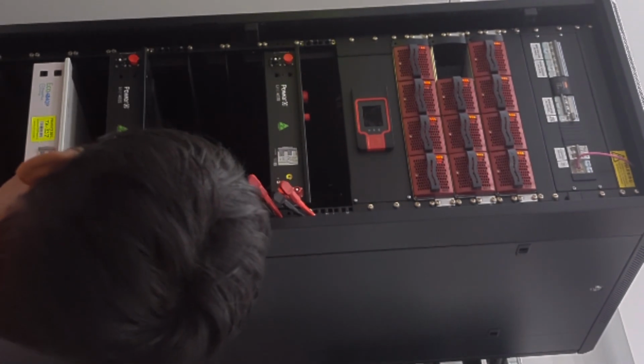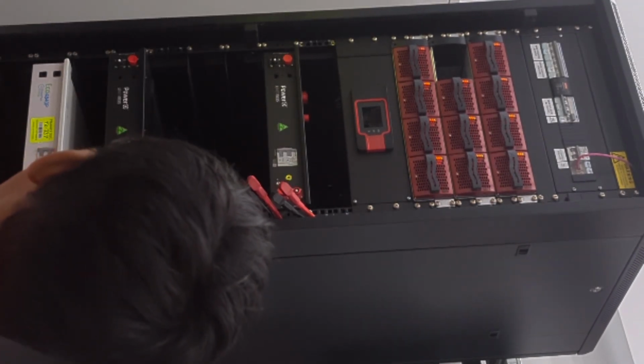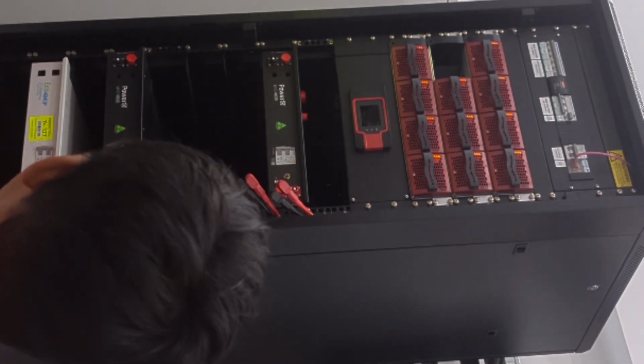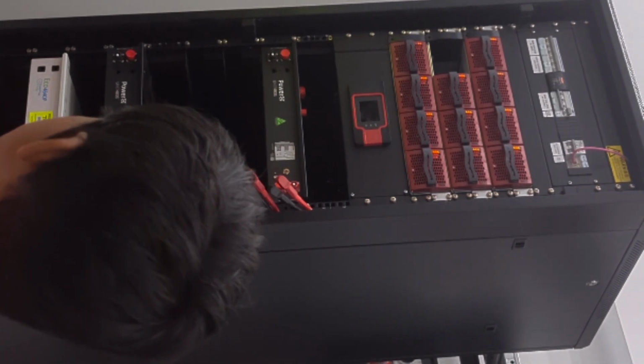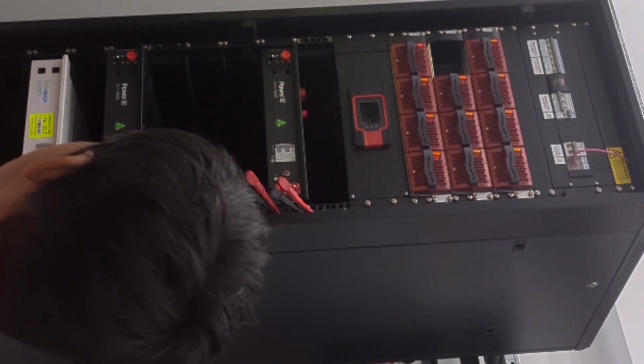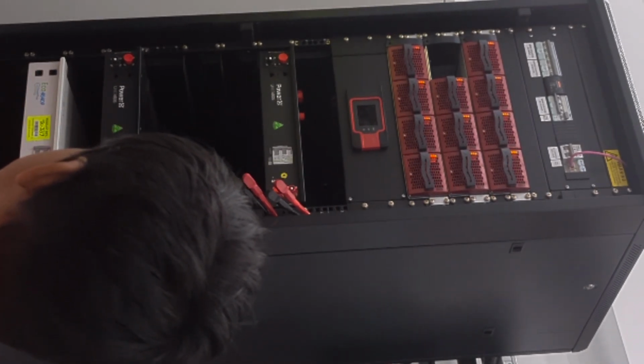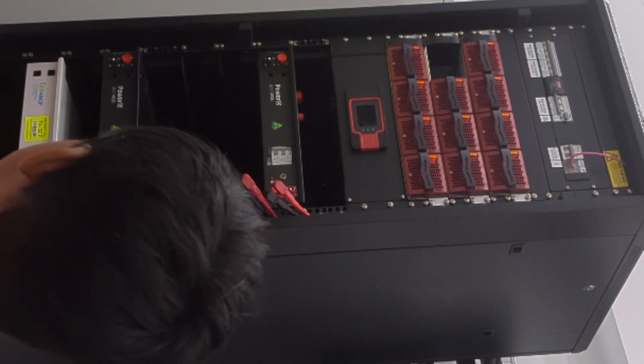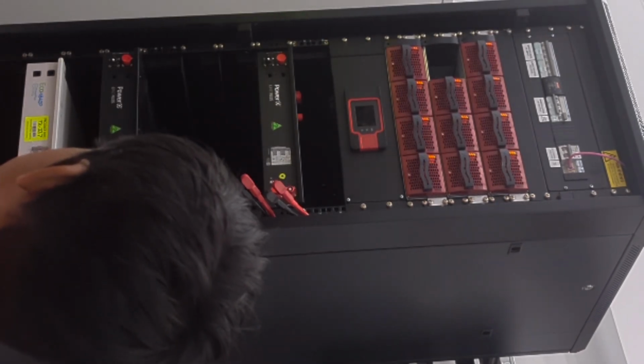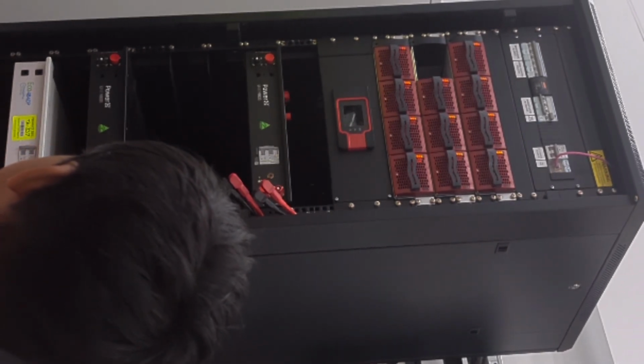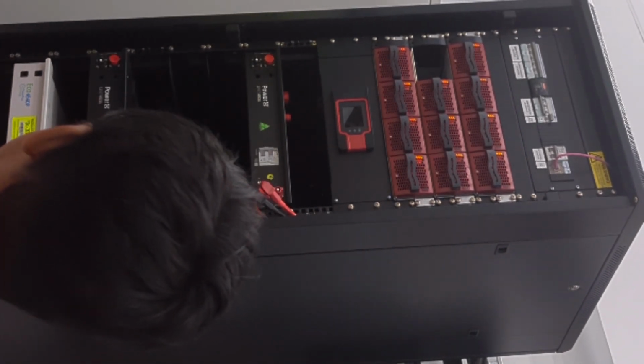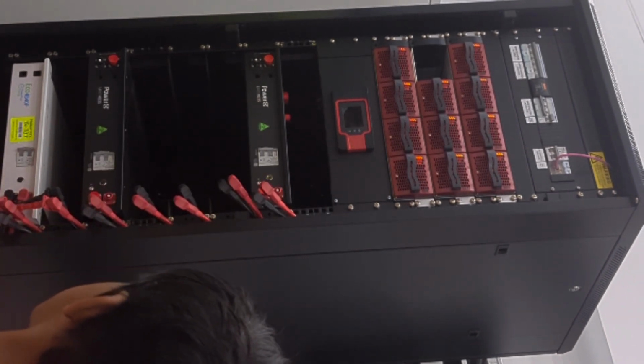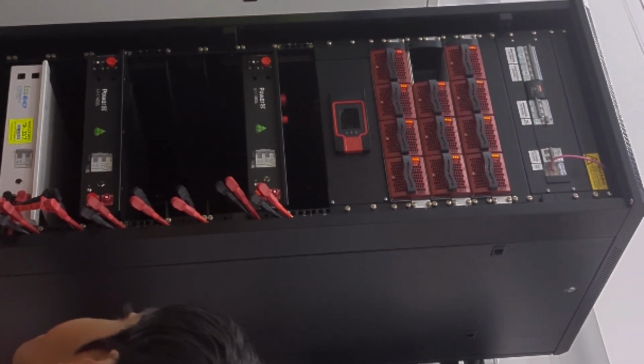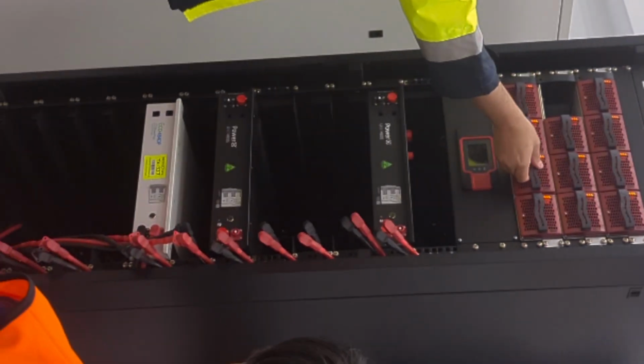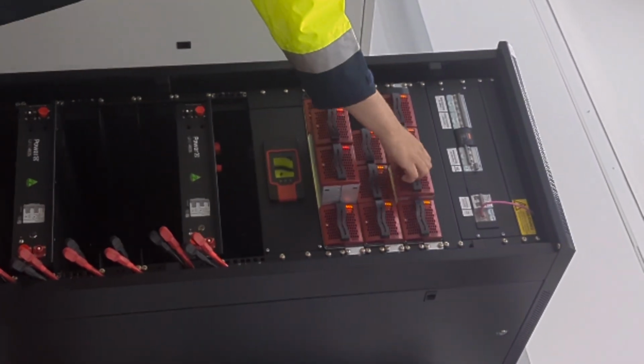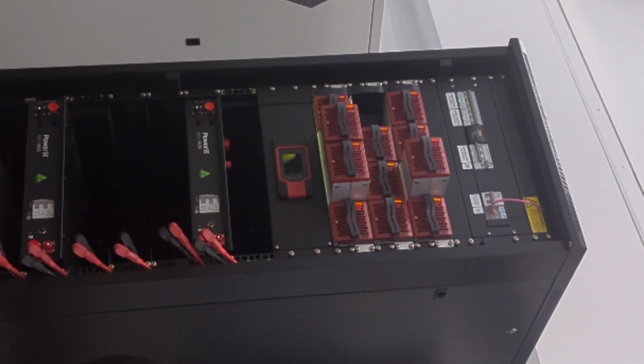And the second inverter is always forming a microgrid. So it's a true UPS. There's no switching or changeover. If the grid goes down, the microgrid is always running. The grid side is effectively always looking for power. If you take power away from the grid side, it doesn't affect the microgrid side, it carries on. So this is what you use in your critical infrastructure projects, stuff where you just absolutely cannot afford a power failure. You could lose multiple inverters and multiple phases, and the rest of the inverters will carry on.